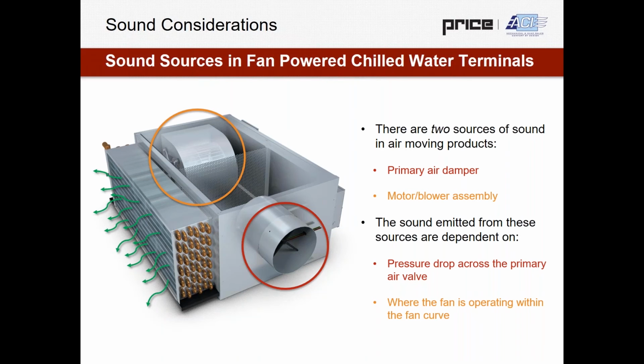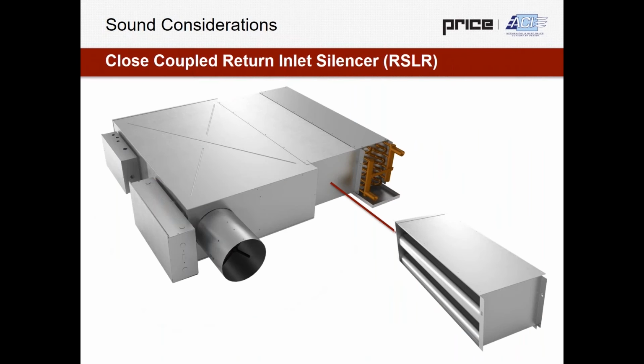And because of this, at Price, we've looked into many different ways of trying to find the best solution to mitigate, especially radiated noise for this equipment. And we settled on what we call our close-coupled return inlet silencer, or our RSLR, which is essentially a sound trap that fits downstream of the water coil and is sandwiched in between that water coil and that motor blower and primary air valve.